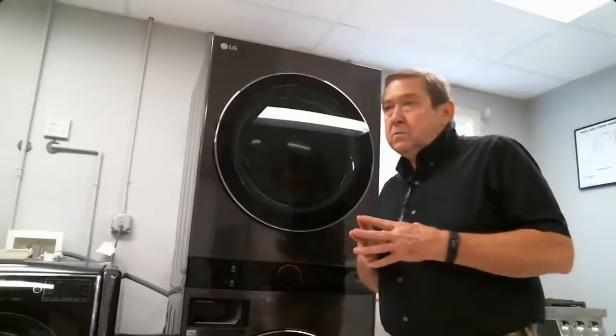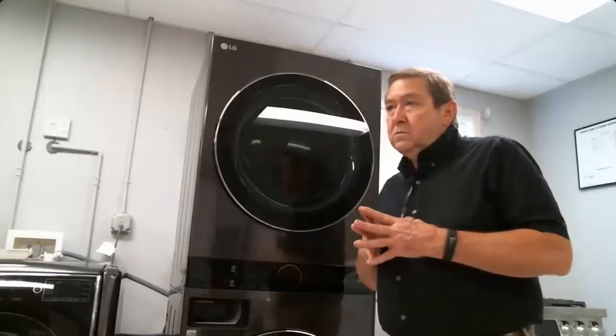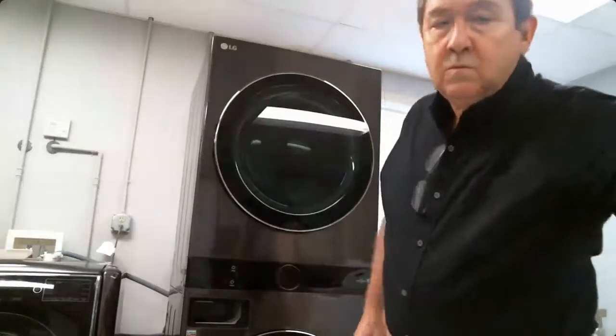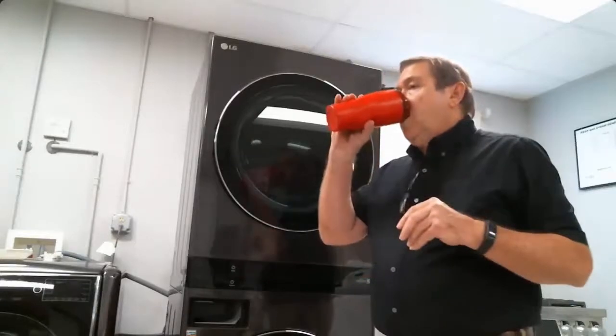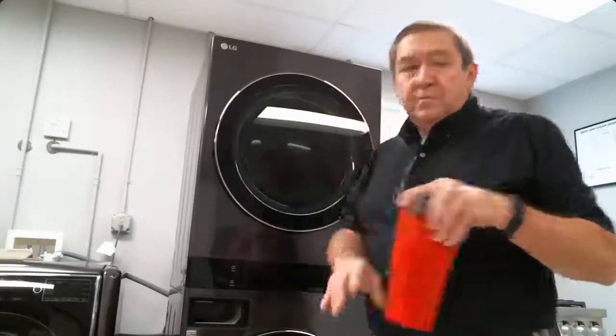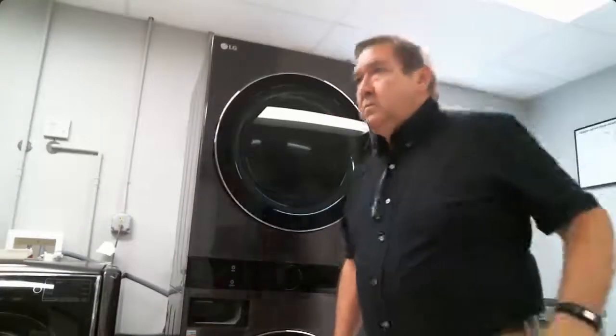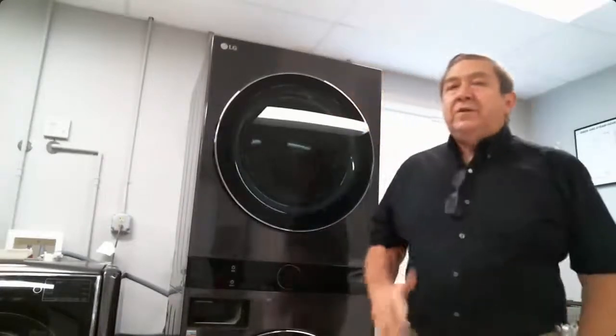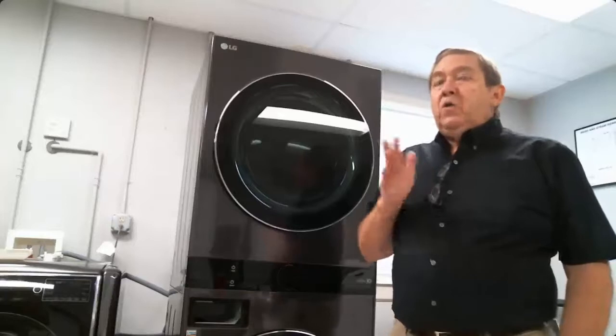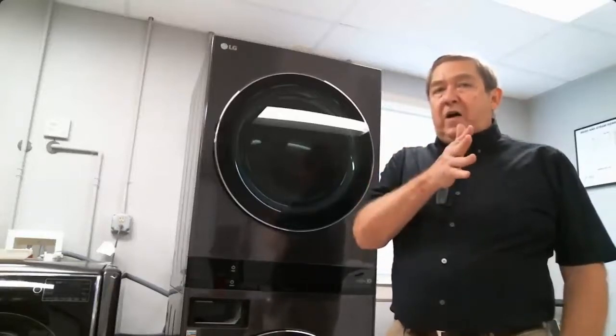Okay, since we didn't get to this question at the time, I'm not sure where he was referring, but it says, then you cannot know if the water valve is bad. And it might have been talking about it's 12 volts during the test, but it's only about 5 or 6 during actual operation. Yeah, so the simplest thing I can tell you is you can check it from the board, or you can check it right at the valve itself. I typically say that in a normal cycle, we're going to send 5 volts DC there. But my point was, when you go into the test mode to check it, we don't send 5 volts. We send higher voltage, about 10 volts. And that might be just enough to go ahead and open that valve.